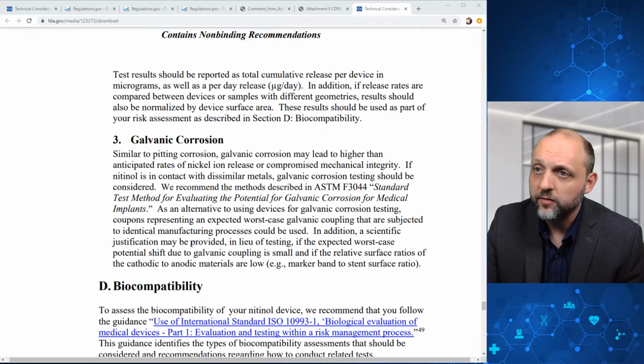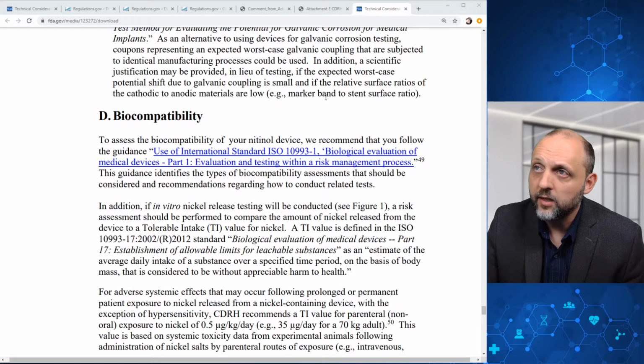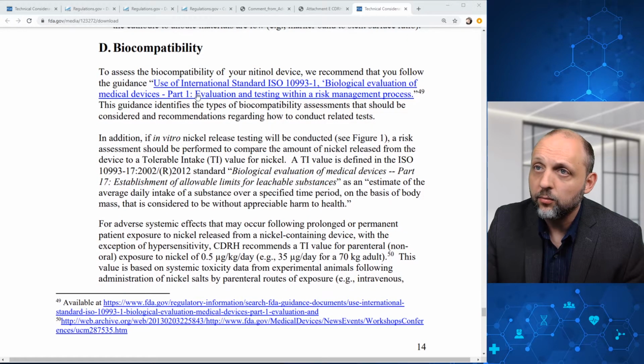In addition, a scientific justification may be provided in lieu of testing if the expected worst-case potential shift due to galvanic coupling is small and if the relative surface ratios of the cathodic to anodic materials are low. And here they give an example of a marker band to stent surface ratio. And then in terms of biocompatibility, FDA references the biocompatibility biological evaluation guidance in terms of ISO 10993-1. And in addition, if in vitro nickel release testing will be conducted, a risk assessment should be performed to compare the amount of nickel released from the device to a tolerable intake value for nickel.